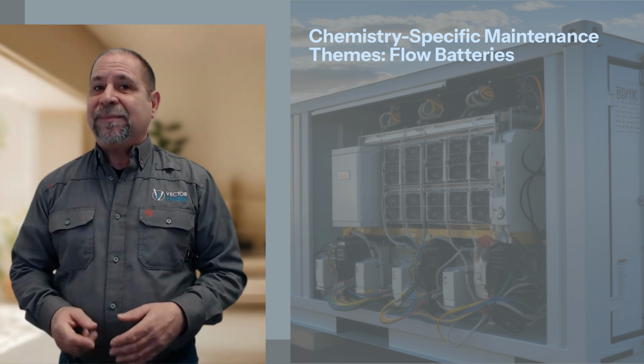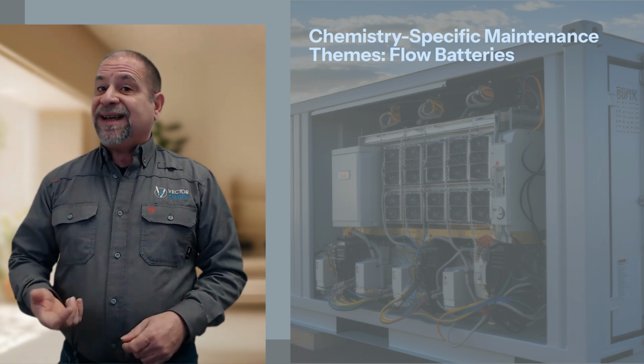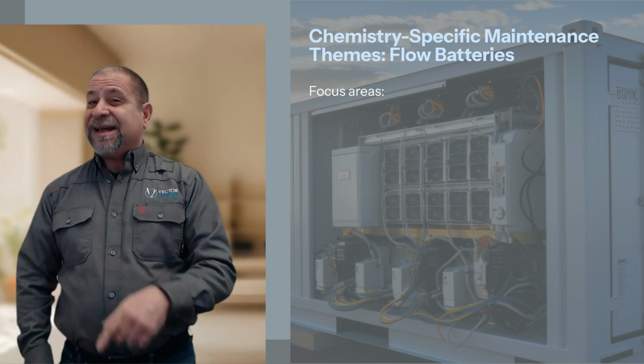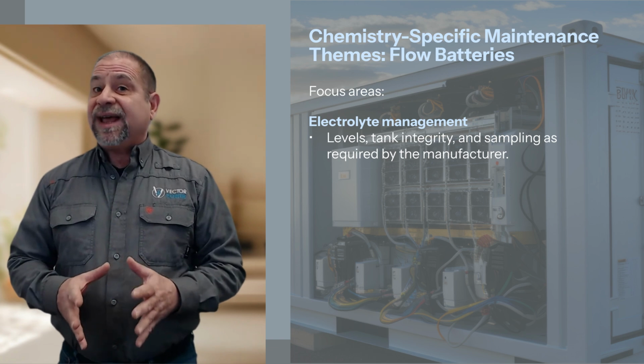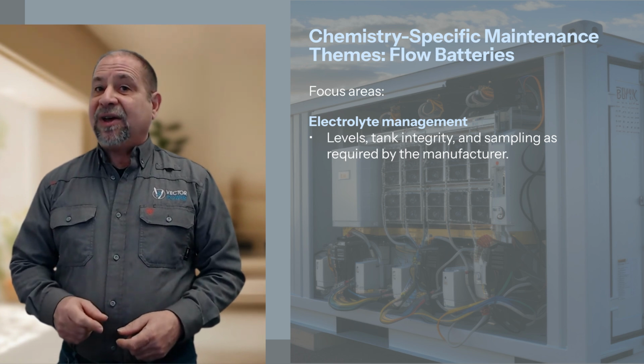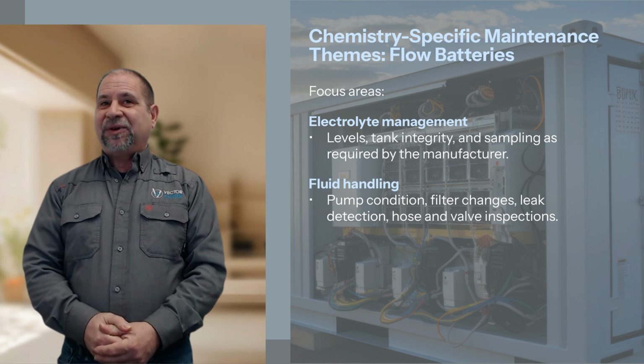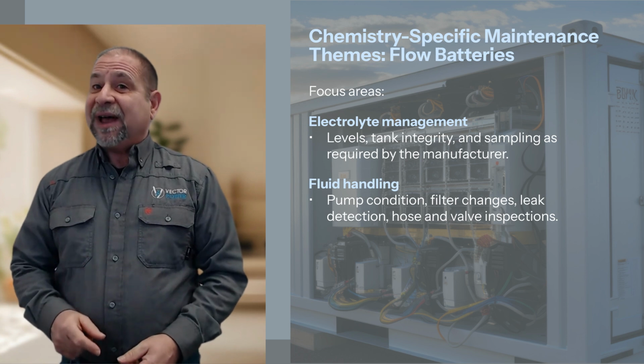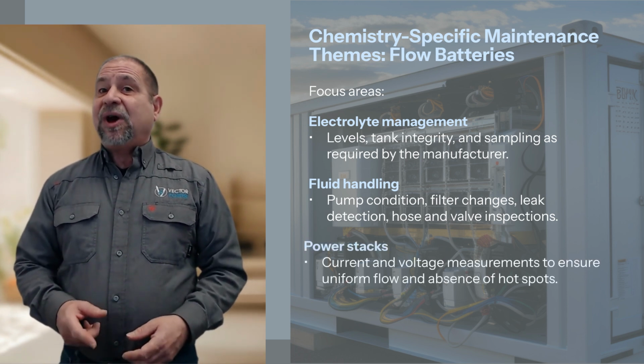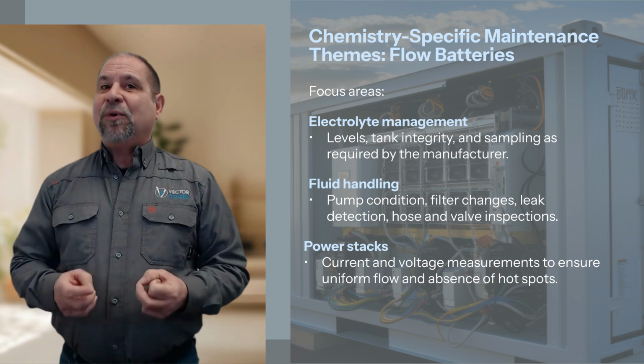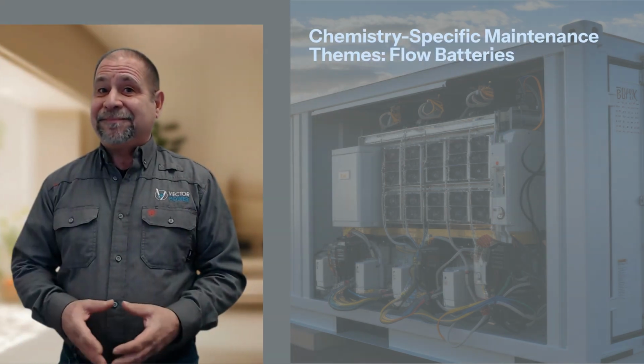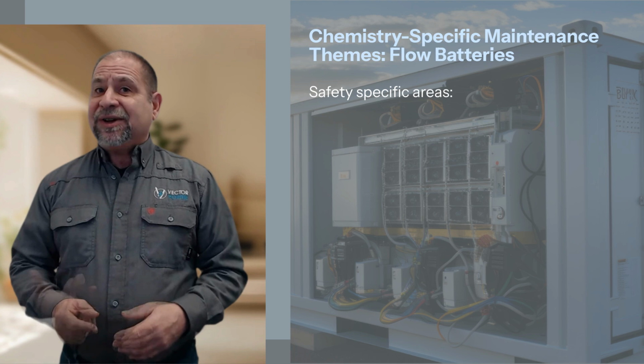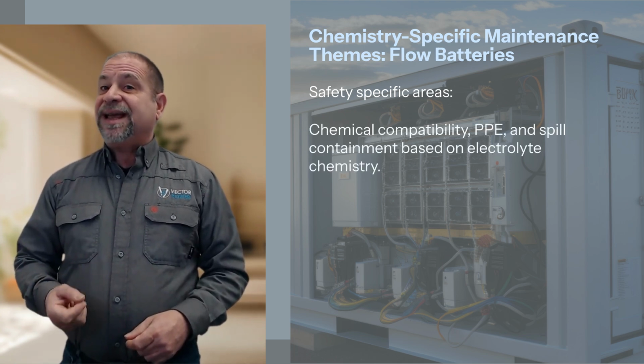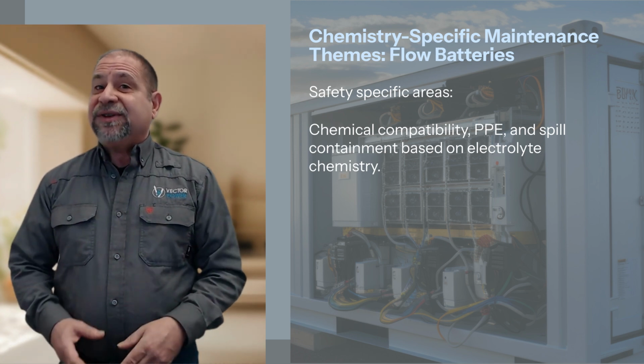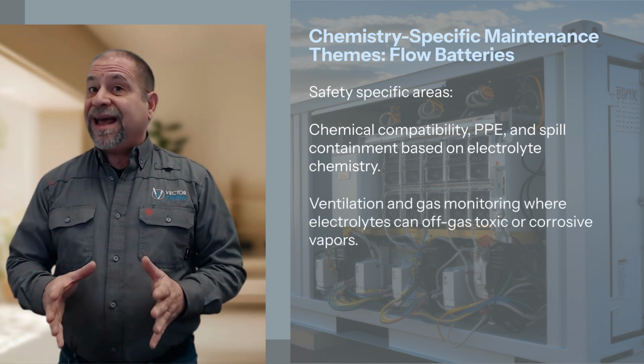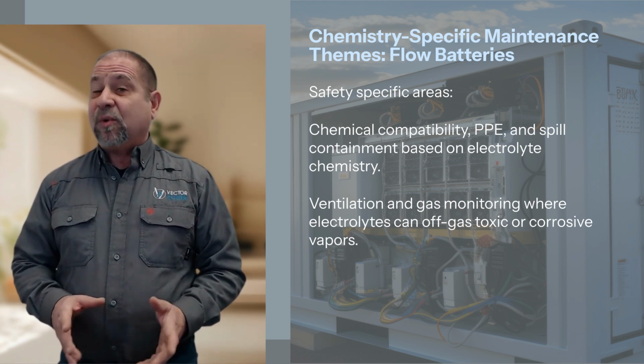Moving on, we will look at chemistry-specific maintenance themes for flow batteries. Focus areas will include electrolyte management, checking levels, tank integrity, and sampling as required by the manufacturer. Fluid handling. Check pump condition, conduct filter changes, leak detection, hose and valve inspections. Power stacks. This will involve current and voltage measurements to ensure uniform flow and absence of hot spots. Safety specifics areas of focus include checking chemical compatibility, PPE, and spill containment based on electrolyte chemistry, and ventilation and gas monitoring where electrolytes can off-gas toxic or corrosive vapors.